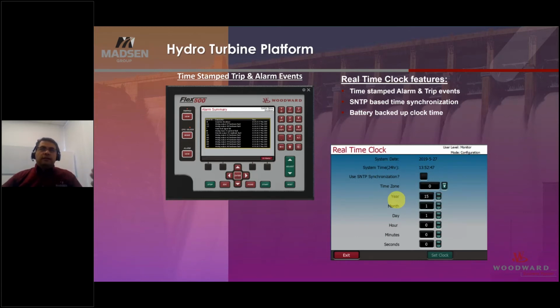Which caused the trip? Is it actually the governor itself that is causing the trip, or something else? Because all the trips and alarms come synchronized together, using the timestamp you are able to define where the problem comes from, and that helps with the diagnostic if you have a bigger issue in the plant.